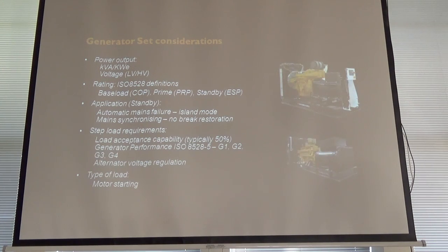So I'll give them options on maybe multiple units as opposed to a single unit. If you've got 3 MVA power requirement, often it's best with 2 smaller 1.5 MVA units. If one's being maintained, you've still got half the power cover. Things like that come into play. The power density is one thing. Obviously there's a lot of pressure. Sometimes we're putting units within buildings and you've only got very limited space available with the high power output requirement. But again, we look at the constraints associated for a given site and come up with the best options for the customer.